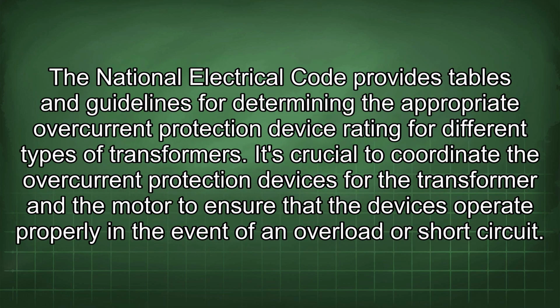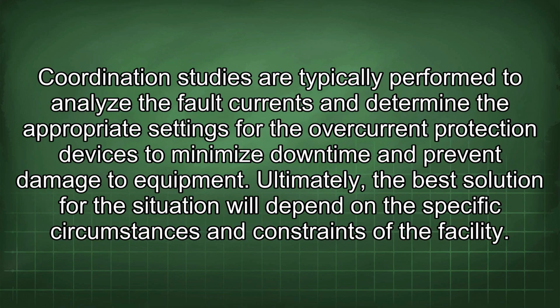The National Electrical Code provides tables and guidelines for determining the appropriate overcurrent protection device rating for different types of transformers. It's crucial to coordinate the overcurrent protection devices for the transformer and the motor to ensure that the devices operate properly in the event of an overload or short circuit. Coordination studies are typically performed to analyze the fault currents and determine the appropriate settings for the overcurrent protection devices to minimize downtime and prevent damage to equipment.